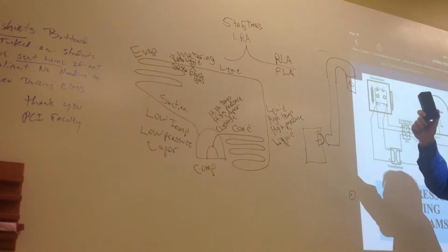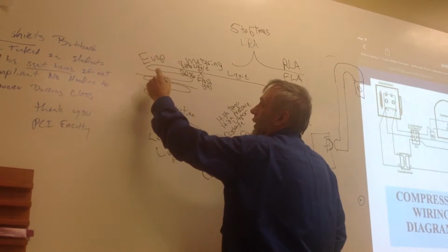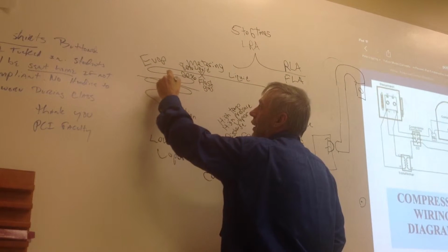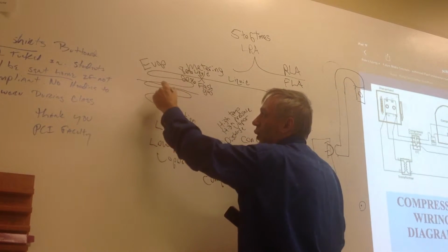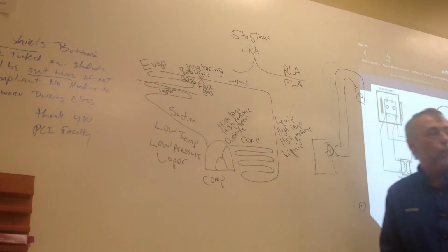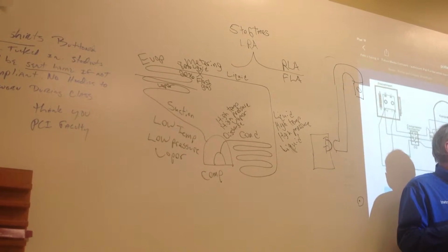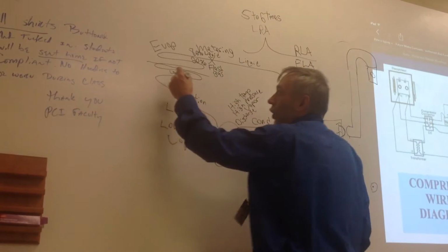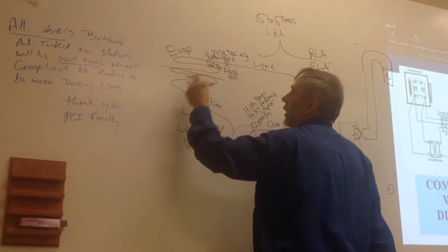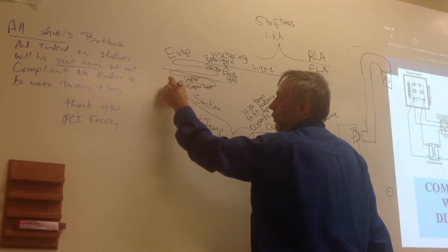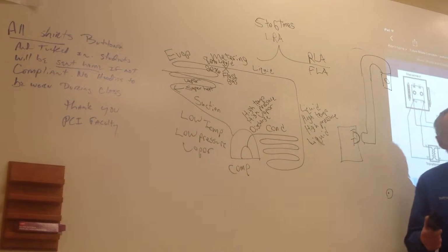All right, so we're up there at the flash gas, and somewhere between 50 and 60% of the way through, this should be all vapor. Now on this last pass or so, it picks something up. What is that called? There's a temperature that it picks up. Superheat, yep. So we can read superheat from right there on that last pass. Usually we would take that superheat measurement within about 6 inches of the outlet of the evaporator.